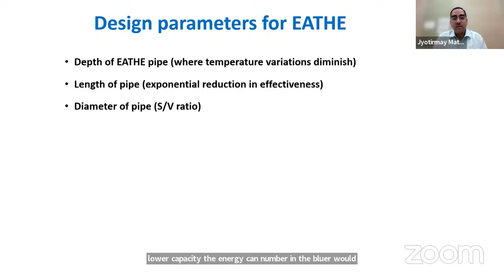Number of pipes, as I said in the beginning, you have to cut down at the optimal length, and therefore decide how many pipes there are. Basically, what matters is the surface to volume ratio of the pipe. More surface per unit volume of air flowing through the pipe means better heat exchange, better performance of the earth air tunnel. So you need to play around between the length, diameter, and determine the right number of pipes to be laid.